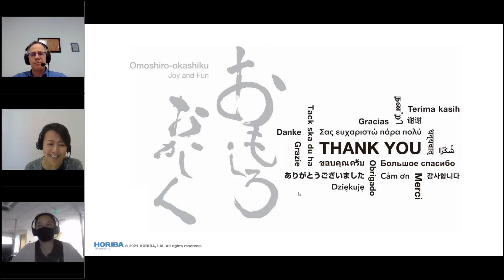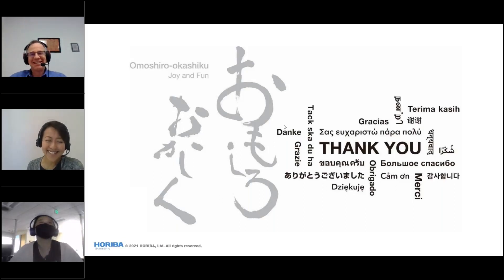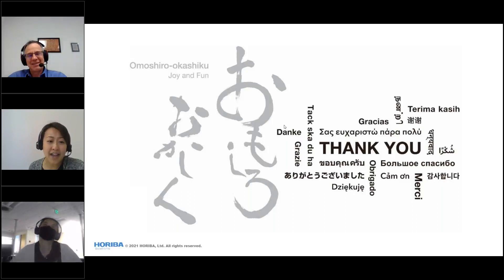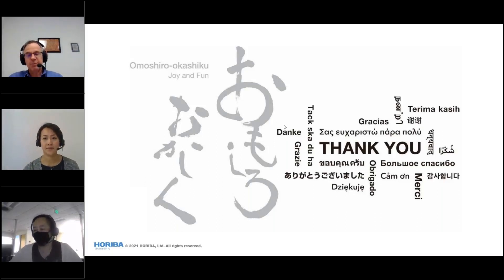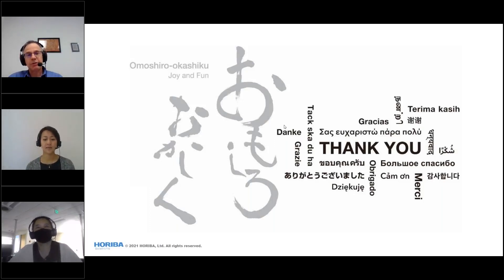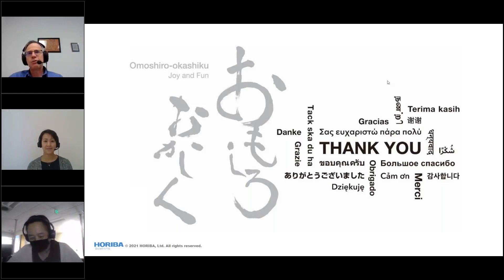One more question: can the LA-960 laser diffraction particle size analyzer output scattering intensity versus scattering angle so the user can use their own model to fit the data? To give enough information to do that, we have to reveal some proprietary design details about the analyzer, so we'd need to structure a non-disclosure agreement around that route. Jeff also asked Una: do we have Particle Finder on the nano Raman systems — the AFM Raman? The analytical part of Particle Finder can go onto AFM Raman with no problem, as it is just an add-on to the software, and that gets you a route to really small sizes.